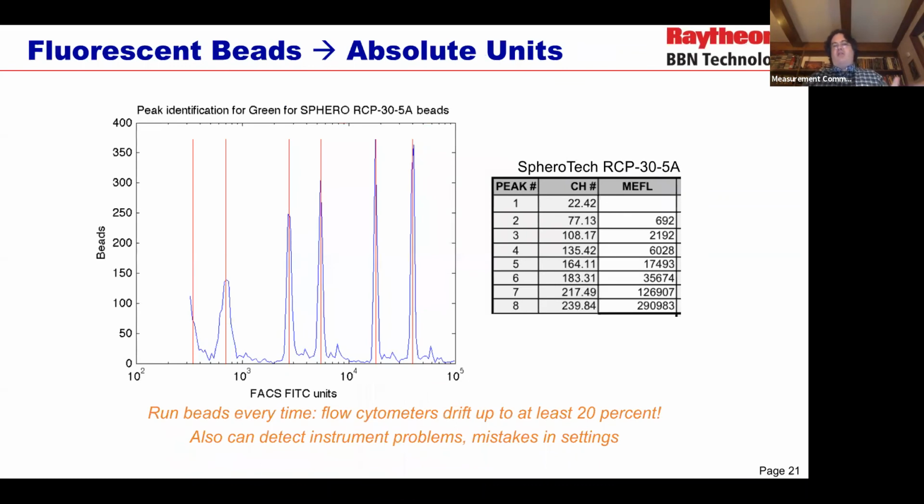Last, whether or not we map things to the same value, we can map each fluorescent channel to absolute units. If we can get everything to the same value, it's ideal. Then we can just map FITC, i.e. the fluorescein, the green-yellow channel. That's the one we recommend because it's the most common, most standardized channel, into absolute units.